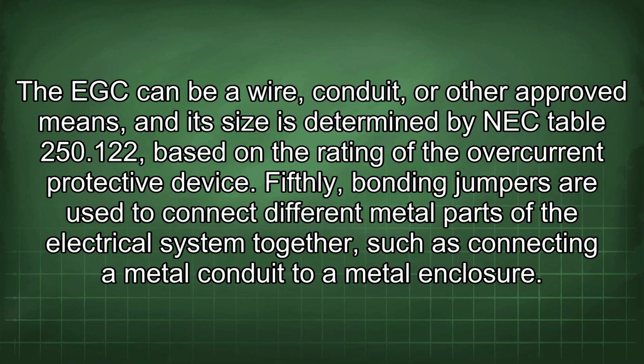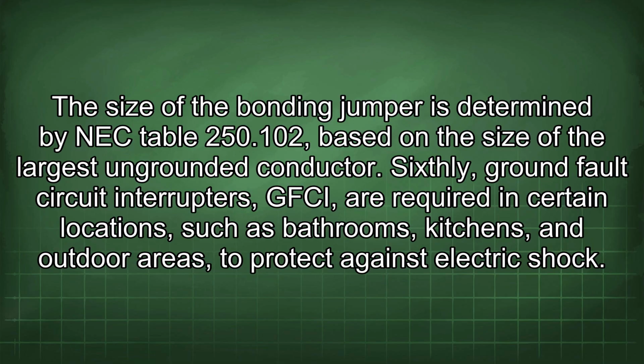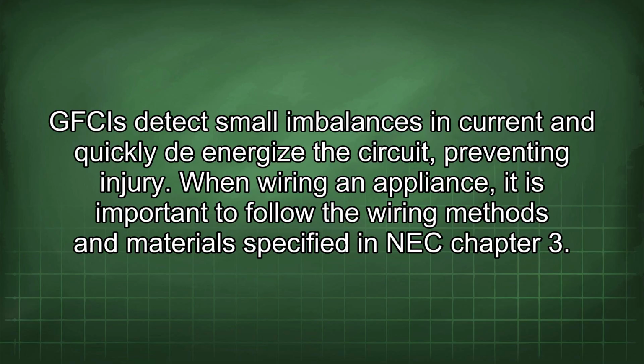Fifthly, bonding jumpers are used to connect different metal parts of the electrical system together, such as connecting a metal conduit to a metal enclosure. The size of the bonding jumper is determined by NEC Table 250.102 based on the size of the largest ungrounded conductor. Sixthly, ground fault circuit interrupters (GFCI) are required in certain locations, such as bathrooms, kitchens, and outdoor areas, to protect against electric shock. GFCIs detect small imbalances in current and quickly de-energize the circuit, preventing injury.